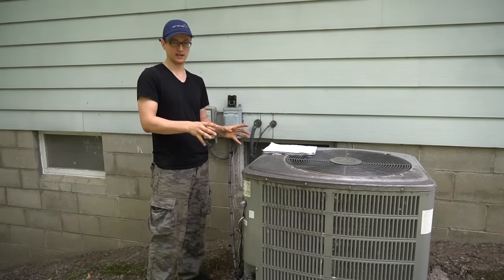I had four calls where the evaporator coil was fully plugged — either somebody forgot to put a filter in, hadn't changed it in a long time, or the filter wasn't covering the whole duct area. You can clean that yourself but it can be difficult; a lot of people hire a ductwork company to rip the plenum open and vacuum it from underneath. Another one with four calls is a restricted metering device — either a piston or TXV that goes in front of your A-coil. If that's restricted you'll need a technician, as it requires refrigerant gauges and specialized tools.